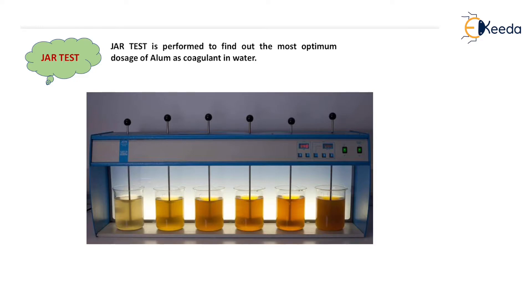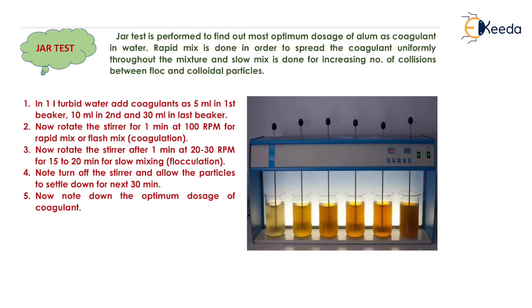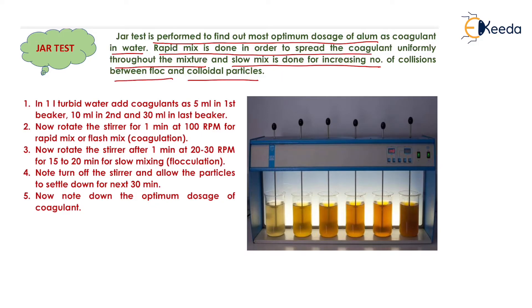To find the optimum dose of coagulant, the jar test is generally performed. Jar test is performed to find out the most optimum dosage of coagulant in water. Rapid mixing is done in order to spread the coagulant uniformly throughout the mixture, and slow mixing is done for increasing the number of collisions between floc and colloidal particles. Fast mixing is for spreading the coagulant uniformly in the water, and slow mixing is done to make all the particles come in contact with each other and form heavier flocs.